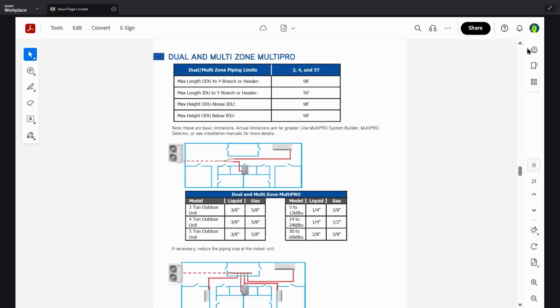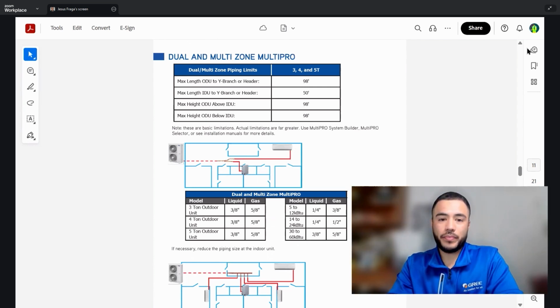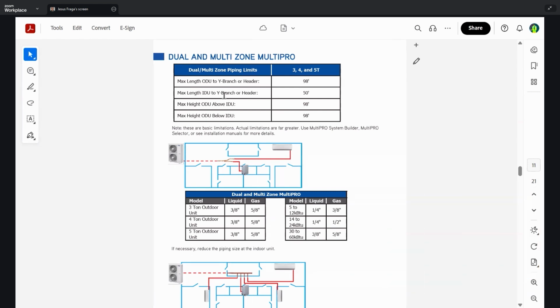So our dual and multi-zone MultiPRO. Here goes some more values of maximum piping lengths for the MultiPRO R32. So we have a max length of ODU to Y branch. We know that's 98 feet. Max length IDU to Y branch or header is 50 feet. Max height ODU above IDU is 98 feet. And max height ODU below IDU is 98 feet.